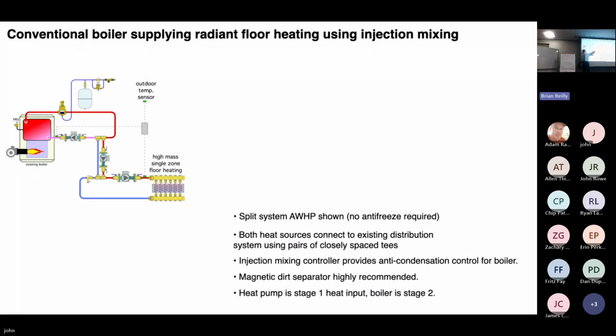We've got a loop down here with a circulator, so we've got water spinning around here, delivering whatever we load onto it. We've got a boiler up here in another loop, generating heat. This is the bridge between where the heat's being created and where the heat needs to go. And by controlling the speed of that circulator, if that circulator is off, there'll be 0 heat transfer across here. And the reason is the closely spaced tees.